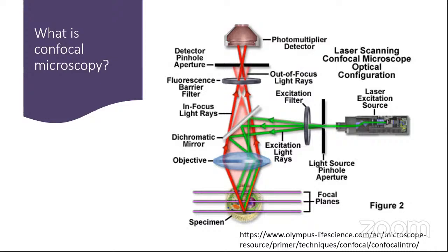Confocal basically deals with having a con focus. So where you are focusing your excitation beam, you are getting it back and putting a pinhole at the back focus, at the sample plane, at the image plane, so that you are only collecting from the specific point that you are interested in. And typically you do that by putting a pinhole aperture right in front of the photomultiplier.